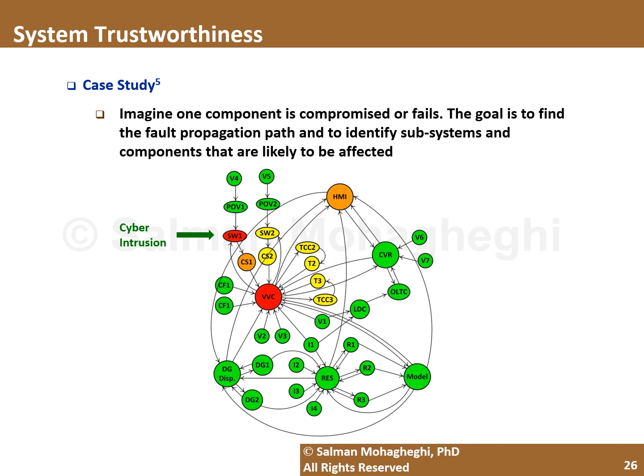So as an example, we said that conservation voltage reduction will be connected to the HMI, the human machine interface. You will be reading data from VT number 6 and VT number 7, the voltages, and you also exchange information with the OLTC, the tap changer, with that transformer at the substation, and you will send and receive information or share information with the voltage VAR control module. Likewise, the voltage VAR control module works with the switched capacitors and reads information through the different voltmeters, and things like that.